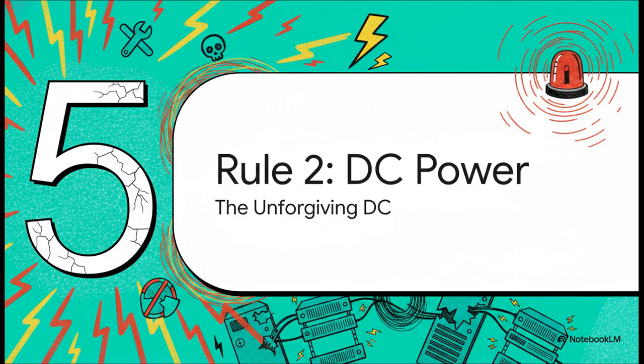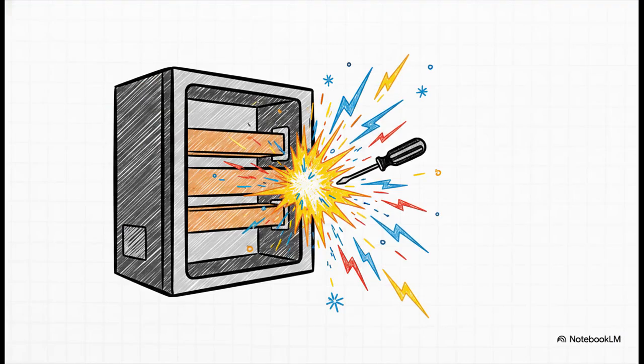Section 5, Rule 2, High Current Power and the Unforgiving DC. Moving deeper into the danger zones, we arrive at the telecom power systems, where a little bit of overconfidence can lead to a disastrous human-induced outage, or much worse, permanent injury. Look, DC power is completely unforgiving. Unlike the household AC power you're used to, which constantly crosses zero voltage and trips the breaker easily, Telecom DC provides a relentless, continuous flow of energy with absolutely no fast trip protection.